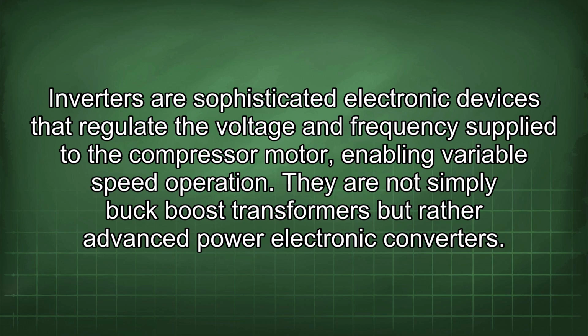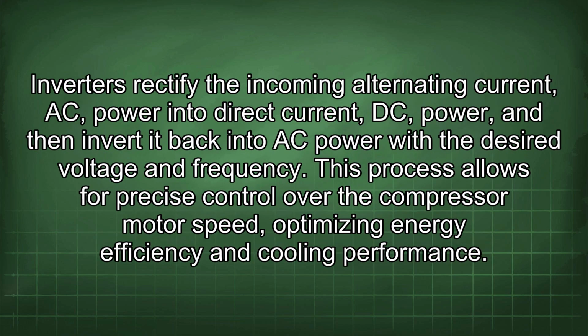They are not simply buck-boost transformers but rather advanced power electronic converters. Inverters rectify the incoming alternating current (AC) power into direct current (DC) power and then invert it back into AC power with the desired voltage and frequency. This process allows for precise control over the compressor motor speed, optimizing energy efficiency and cooling performance.